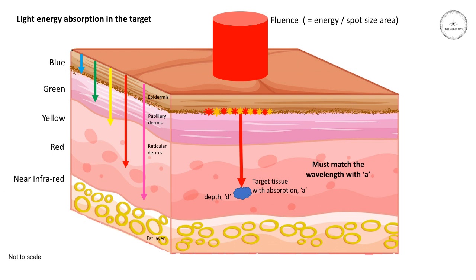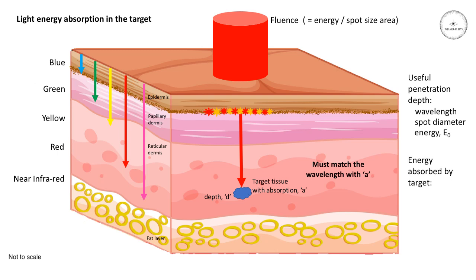When we discussed the penetration depth of light previously, it was purely with respect to the wavelength. A more useful definition is the useful penetration depth, which depends on the wavelength, the spot diameter, and the energy at the surface. Combined, these give you the fluence or energy density, which tells us the amount of energy which reaches the target depth. The amount of energy finally absorbed by the target depends on the wavelength, the depth of the target, the absorption coefficient of that target, and the scattering coefficient of the surrounding dermal medium.